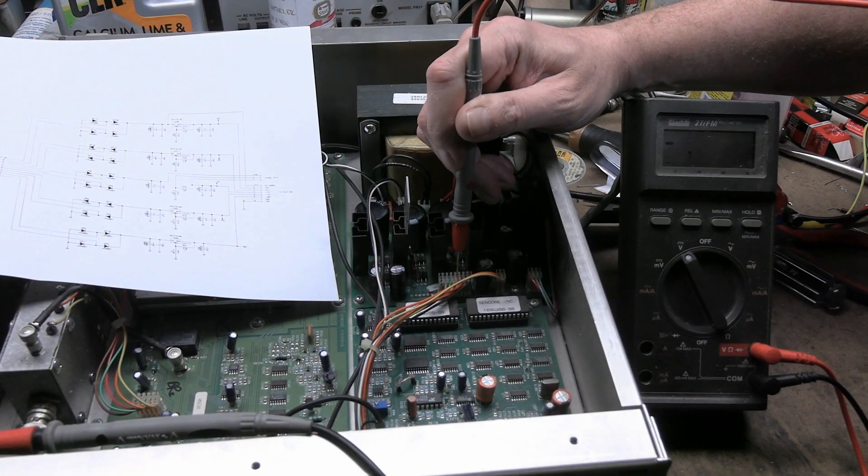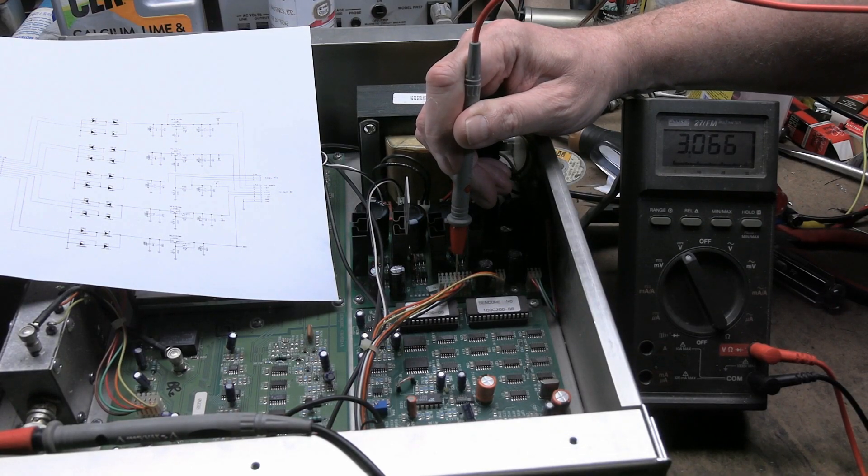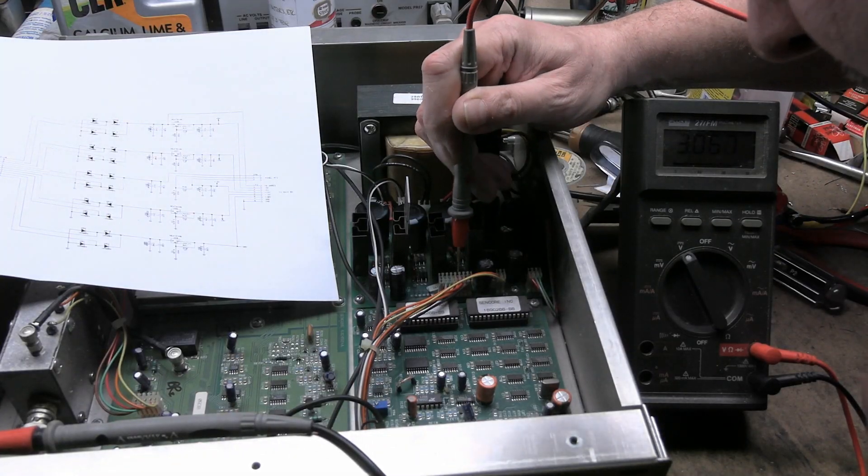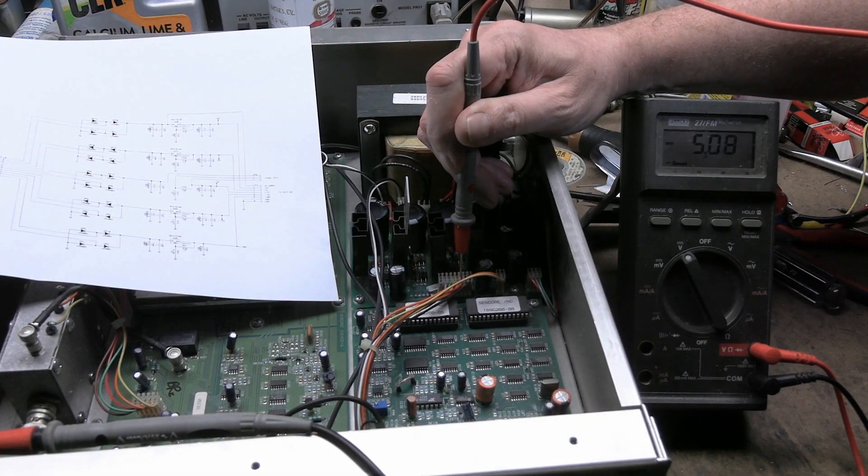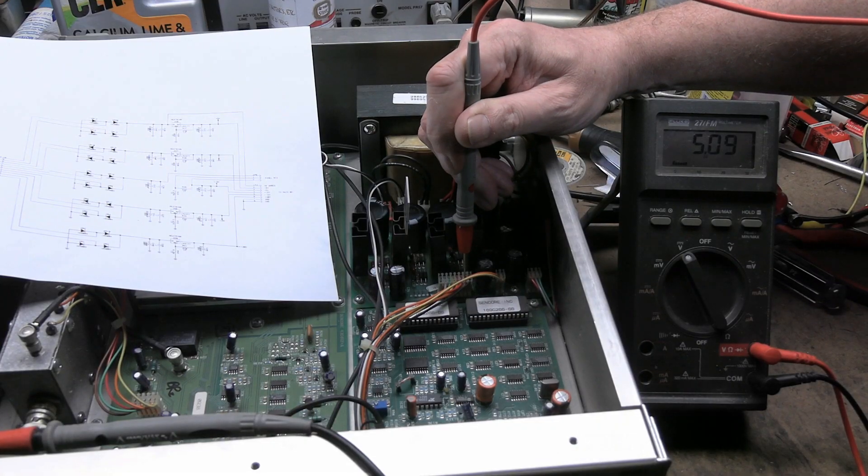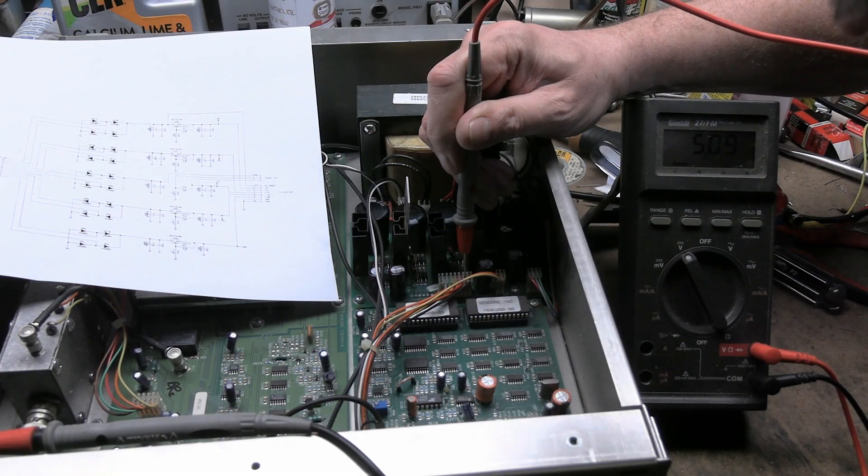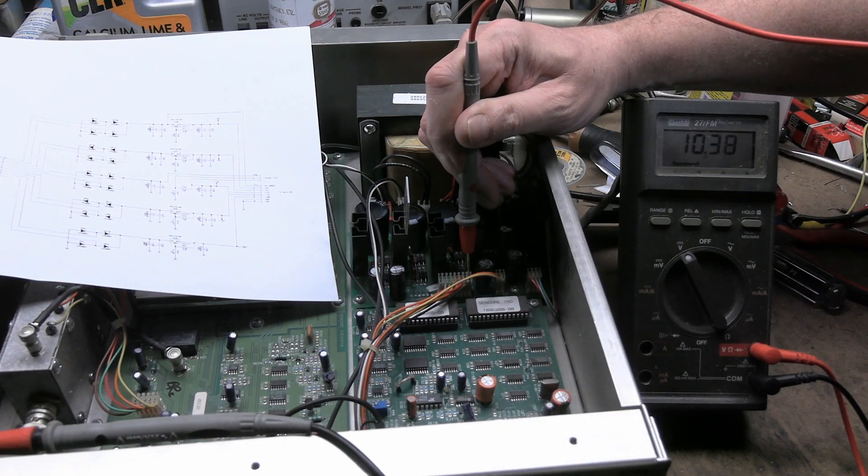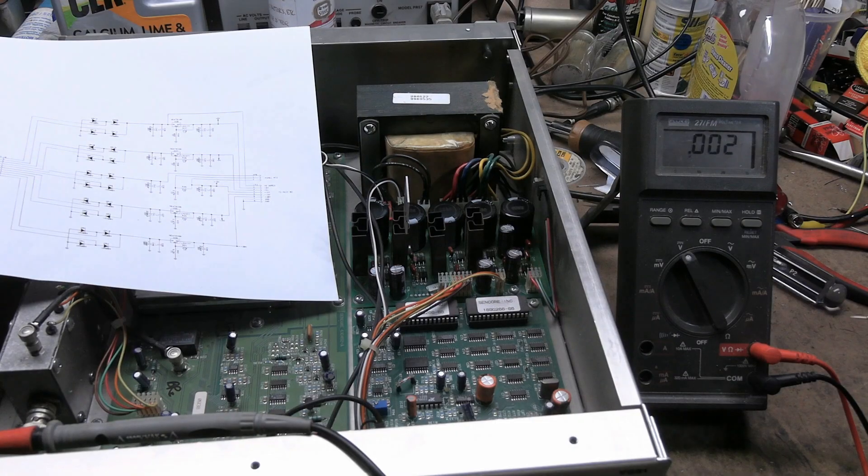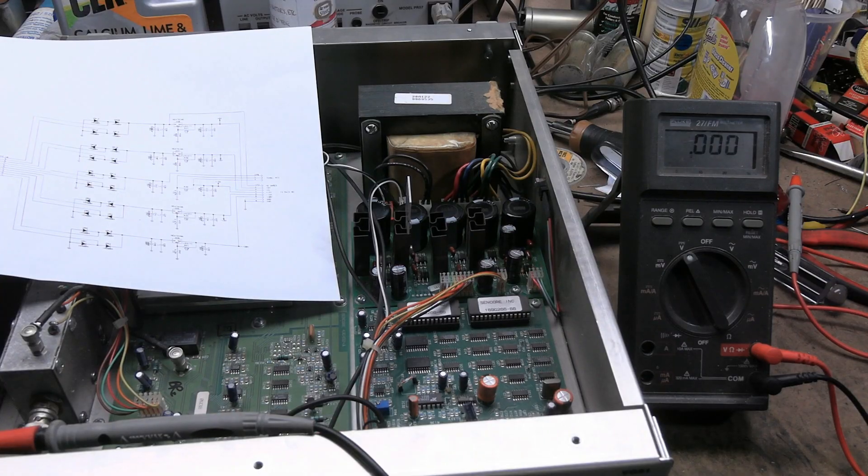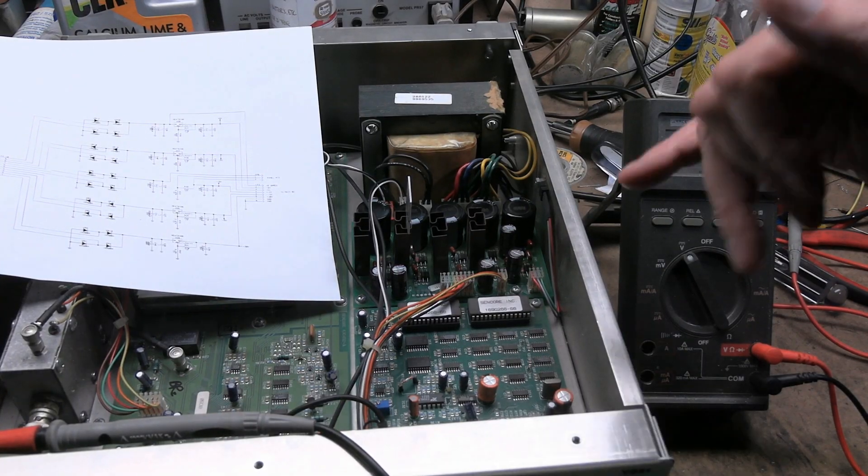This should be plus 15. We have three. Okay, we have a problem there. Let's keep going. It should be minus five. We have minus five. It should be plus five. We have plus five. It says eight volts unregulated, and that's 10. But it could be because this thing isn't fully powered up. That relay hasn't kicked in. Let's power it down. So we have a problem on the plus 15.